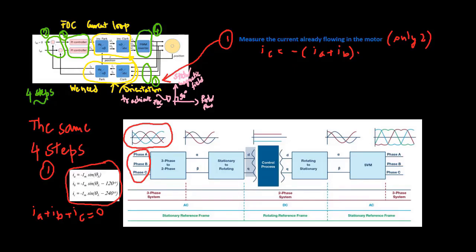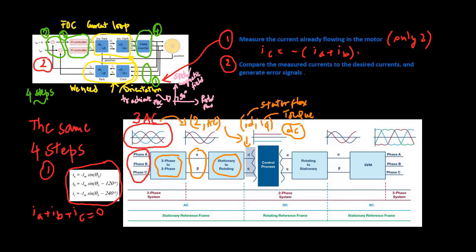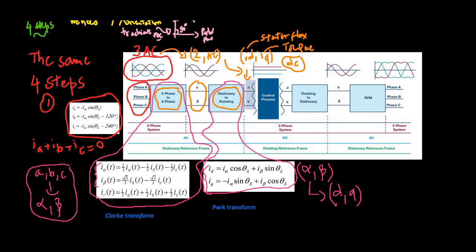These same four steps are also used to do FOC on an AC motor. The main difference is that since AC motors do not have brushes and a commutator, the process must also include the orientation part of the job. Step 1: measure the current already flowing in the motor. In the case of a three-phase permanent magnet synchronous motor, we have three currents to control, but for the FOC algorithm we only need to measure two of these currents. Step 2: compare the measured currents to the desired currents and generate error signals. The desired currents ID and IQ are DC currents, while the measured currents are AC currents.